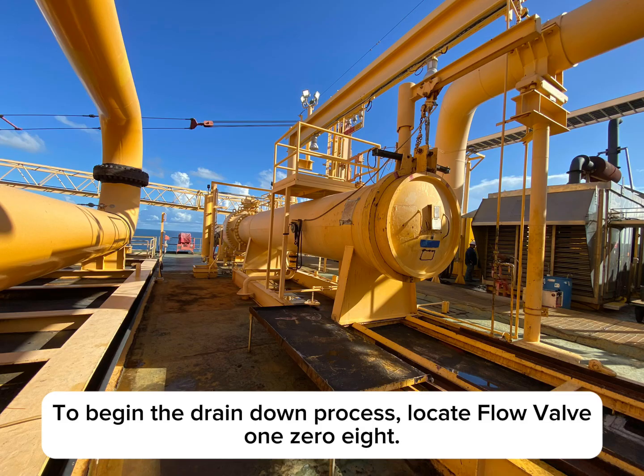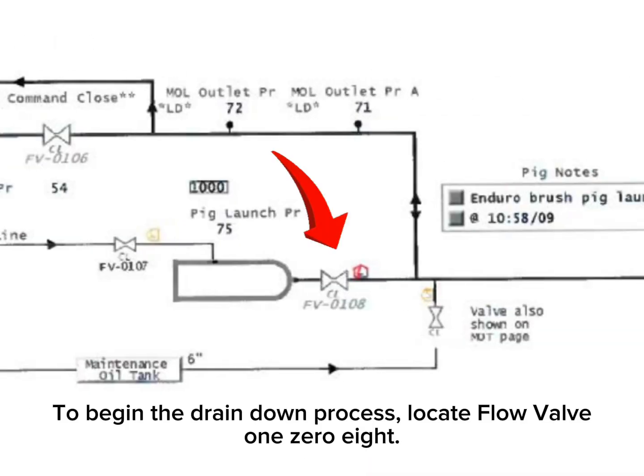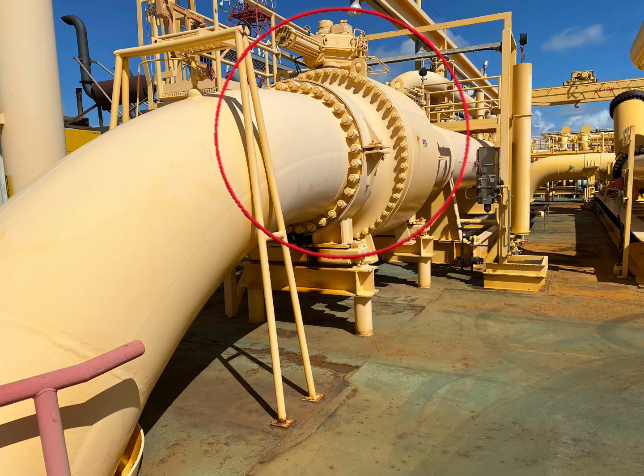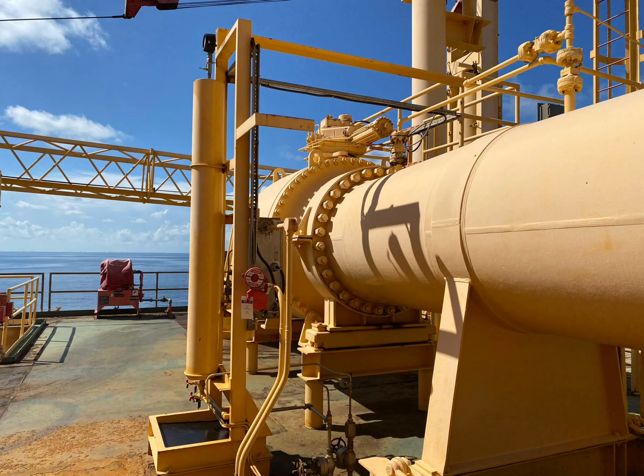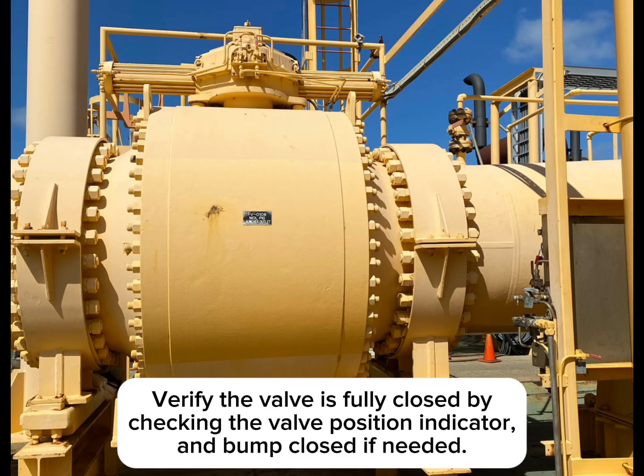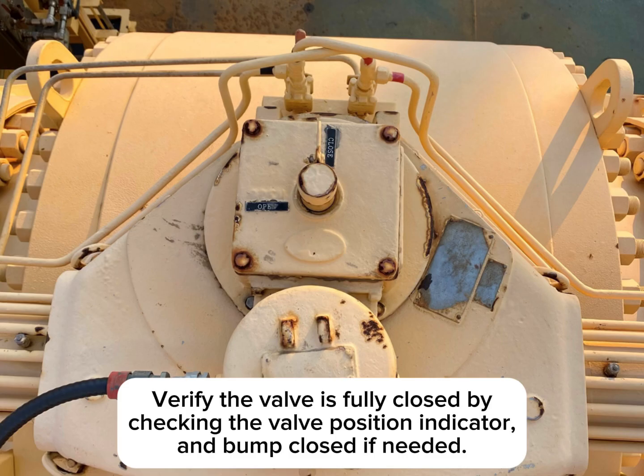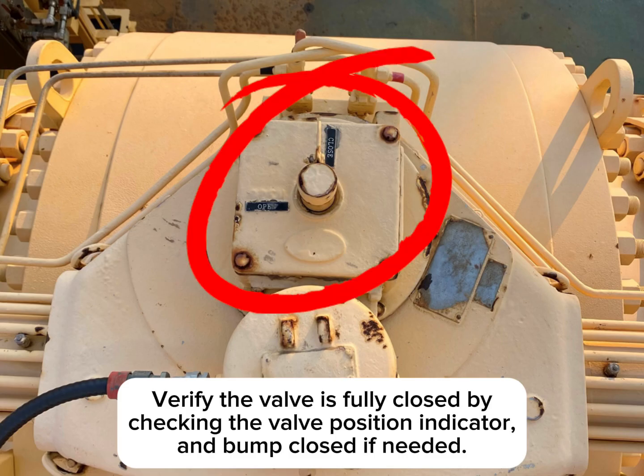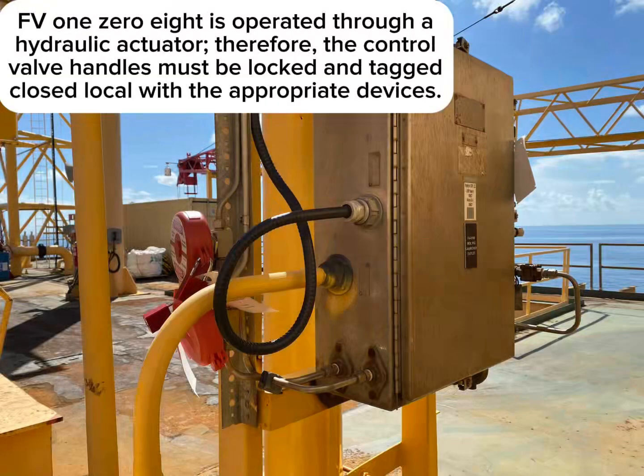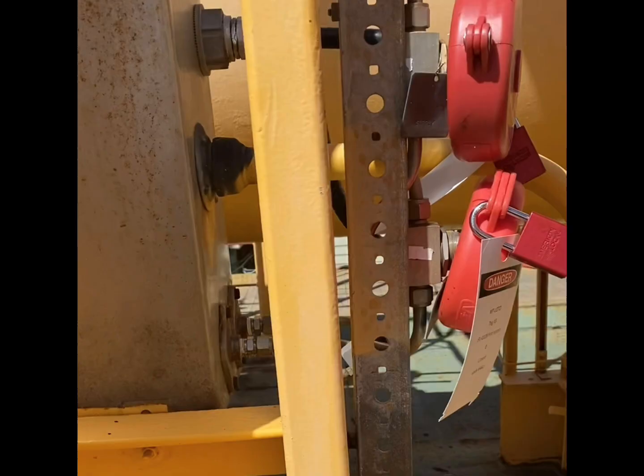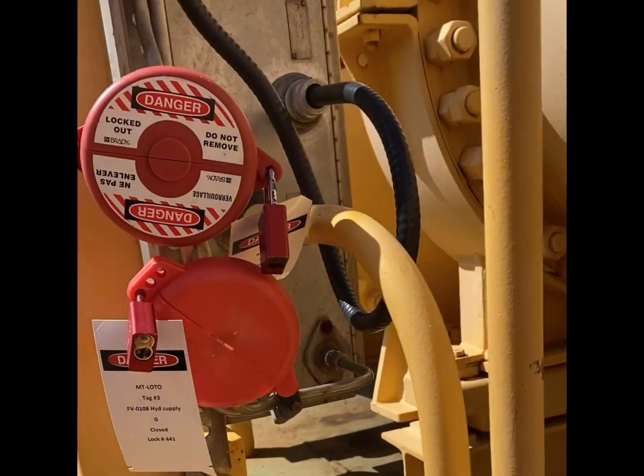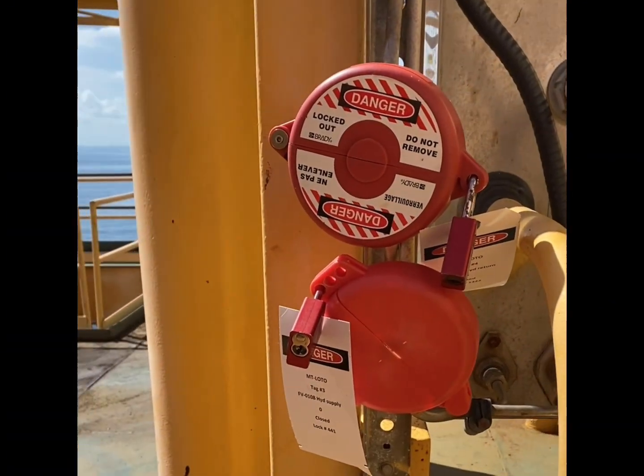To begin the drain down process, locate flow valve 108. Verify the valve is fully closed by checking the valve position indicator and bump closed if needed. FV108 is operated through a hydraulic actuator. Therefore, the control valve handles must be locked and tagged closed local with the appropriate devices.